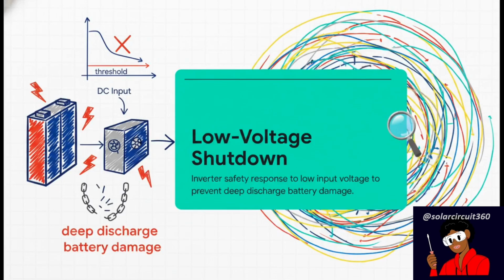Here's the thing. This shutdown is actually a vital protection mechanism. It's meant to save your gear, so it doesn't necessarily mean the inverter itself failed. Basically, your 24-volt inverter is constantly monitoring the DC input voltage coming from your battery bank. If that voltage drops below a certain programmed threshold, bam, the inverter hits the kill switch. It's literally doing exactly what it was designed to do. It's stopping an overly deep discharge that could permanently ruin your battery cells and totally tank their lifespan.